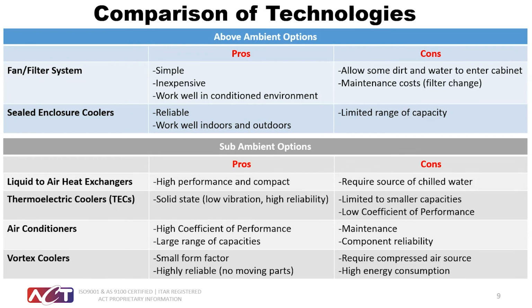The last item shown in the table is the Vortex cooler. Vortex coolers are physically small and easy to package, and also highly reliable because they have no moving parts. One thing to keep in mind is that vortex coolers depend on compressed air to operate, which requires a dedicated air source near the enclosure that is being cooled. Because of the large airflow volumes required, this technology is less energy efficient than others.